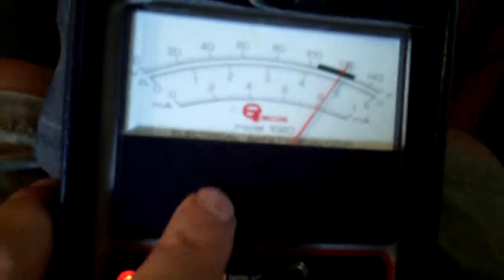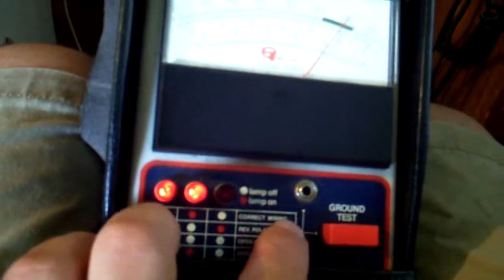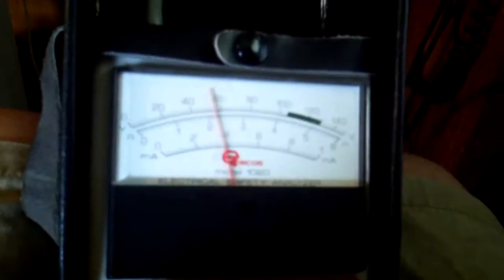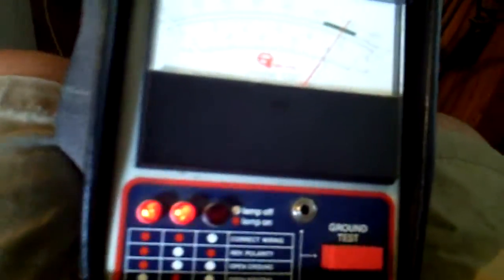You've also got a fuse up here, just a little replaceable glass fuse. So if you get one of these and it's not working right, you might check the fuse. So if you have one of these, that's the simple basic operations of it: leakage current, ground test via the plug, voltage, correct wiring.